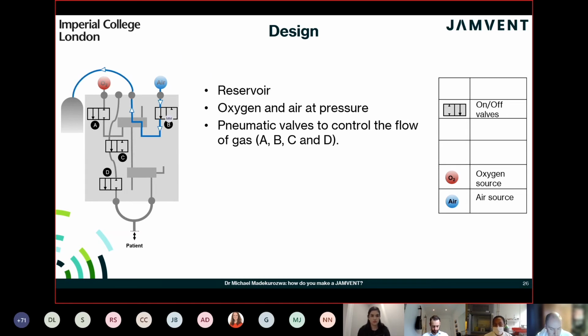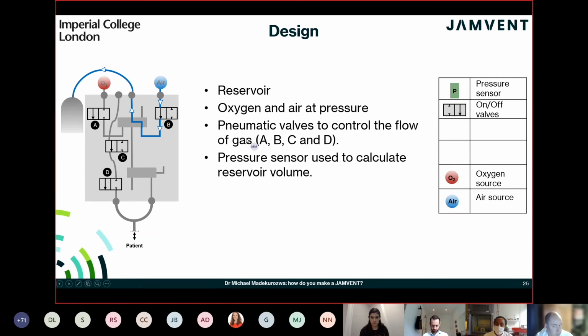So inside the schematic, whenever I show a solenoid in this formation, that's the on position. It's allowing air through it to go into the reservoir. And in this position, that's the off position. It's not allowing air to go through it. There's a pressure sensor inside the system over here, which is used to calculate the pressure in the reservoir, and this is used to titrate a volume for the patient. So this is used to calculate volume via Boyle's law, which Joseph spoke about earlier.